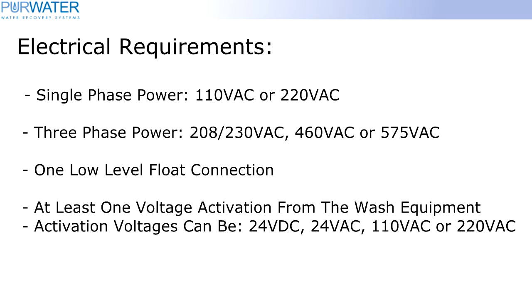To review, the single-phase power can either be 110 VAC or 220 VAC. Three-phase power can be 208/230 VAC, 460 or 575 VAC. There is one float connection. And at least one voltage activation from the wash is required. This can be 24 volt DC, 24 volt AC, 110 volt AC or 220 volt AC.